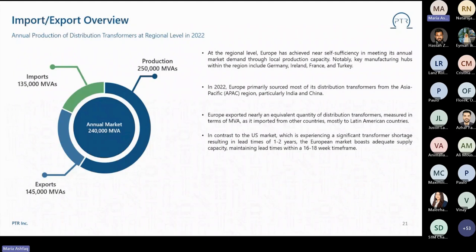If you look at the supply capacity or lead times of distribution transformers in Europe, I'd like to compare it with the US market. In the US before COVID-19, distribution transformer lead times used to be 8 to 10 weeks for both pole and pad mounted. But at present the situation is very bad, and lead times have increased to 1 to 2 years from just a few weeks.